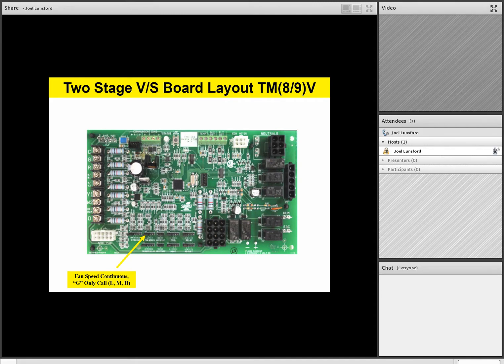Now on this particular board, it doesn't give you a specific fan speed, but please write this down or make note of this. Low is about 35% cooling airflow. Medium is 50% cooling airflow. And high is 100% cooling airflow. So it's a high, medium, low type of thing. But again, that can be selected by the field technician if they want continuous fan with a G only call to the board. So remember, the thermostat is saying, give me the fan only on the G only call. And how fast the fan runs will be determined by that jumper, high, medium, or low. Now, typically from the factory, we ship it on the low, but it is field selectable to 50% or 100% airflow with that field selection.